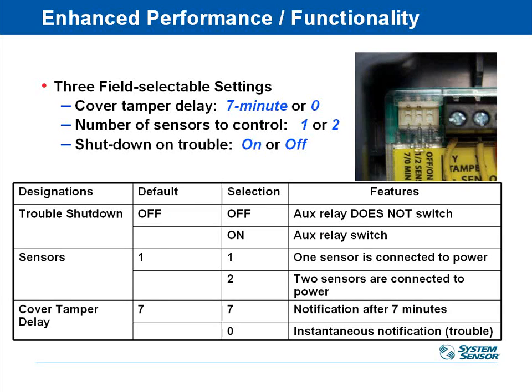There is a dip switch so I can decide if I want my auxiliary relay to not switch or if I want it to switch. And then I have one for tamper delay. By default, there's a 7-minute delay on the cover of these detectors. You can take the cover off, do some work in the detector, and put it back on, and it will not alarm out and shut all the air handlers off unless you did that for more than 7 minutes.